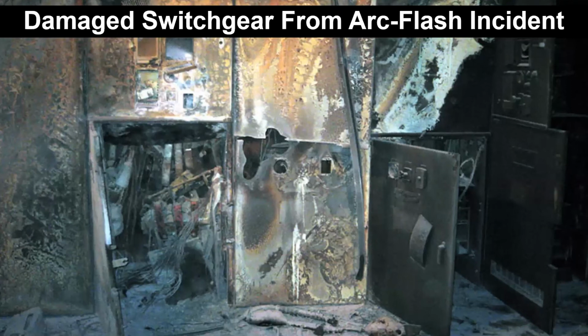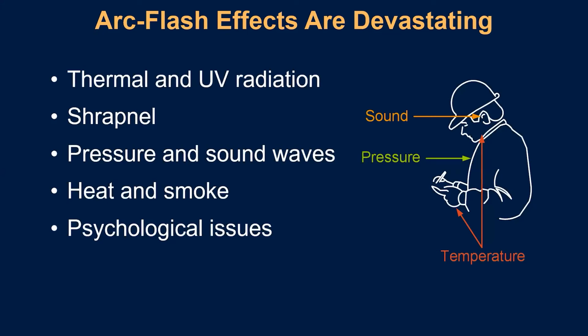And if we start talking about the effects on personnel involved with this equipment, then you can see that there is damage caused by infrared and UV radiation that can cause eye damage. The arc flash is accompanied by a blast, and that blast is powerful enough to knock people off their ladder or just knock them off the ground. And with it comes a lot of melted metal, shrapnel, and fatality that can occur mostly because of burn injuries. You also need to touch upon the fact that post this incident, if technicians or workers survive, they can also have psychological issues. Reports talk about how workers show apprehension at the workplace after experiencing an incident like this, which is pretty understandable considering the effects that they experience.